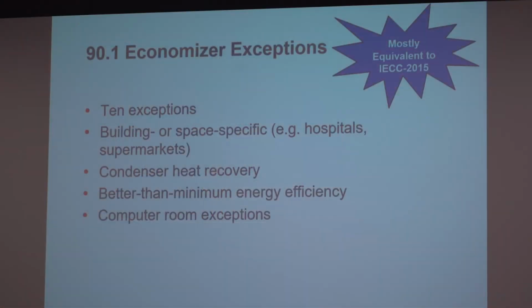There are exceptions. There's 10. It's on the next slide. One of them I already mentioned, which is the dew point control that usually affects hospitals and patient care areas, but it could be other applications. You mentioned something like a process, I think. Condenser heat recovery, if you're doing that, it sort of works at cross purposes with economizers, because the time when you're shedding the cooling load is the time when you wanted to recover the energy from the condenser. So you can't usually have both of those in the same system at the same time. So there's a crosswise exemption there. I already mentioned the energy efficiency thing. There's a better efficiency trade-off table in 90.1.